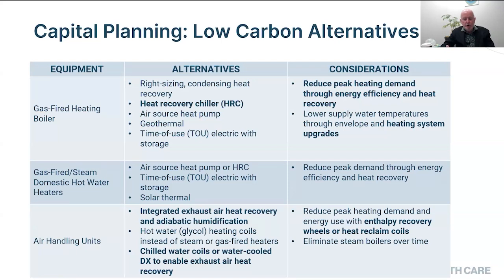We're looking at reducing peak heating demand as well as heating energy consumption through energy efficiency, which is still the vital first step. You've got to be efficient before you can decarbonize. Otherwise, it's just too costly to get the job done. We're going to be looking at air handling units, which reject conditioned air right through the heating season and the cooling season. What are the technologies and how do we actually incorporate those into existing hospitals? Next slide, please, Emily.